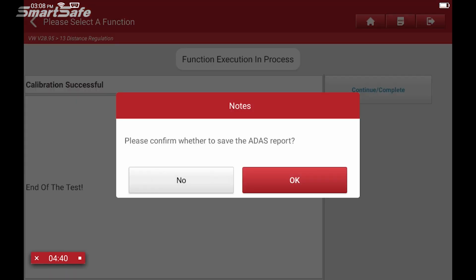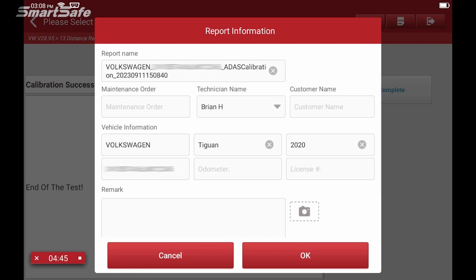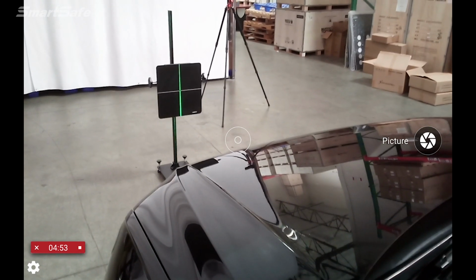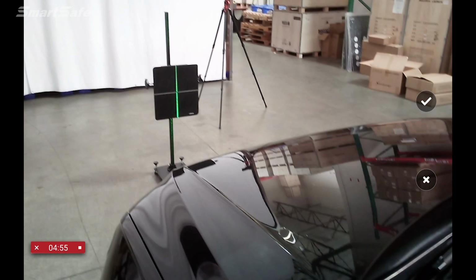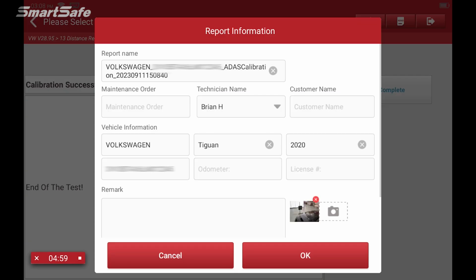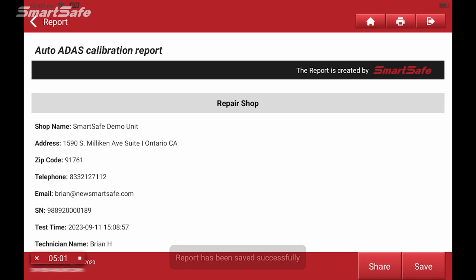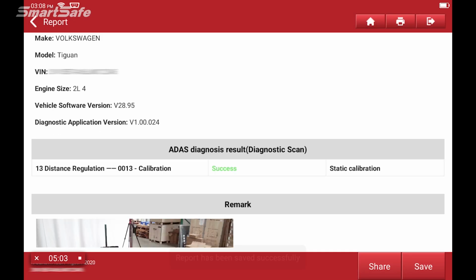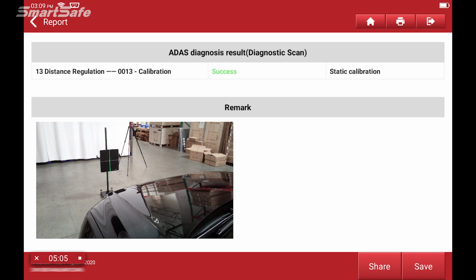We'll save the diagnostics report. Here we can add a photo showing that we actually did the calibration steps, so I'll take a picture with the calibration frame, add that to the diagnostics, and hit save.